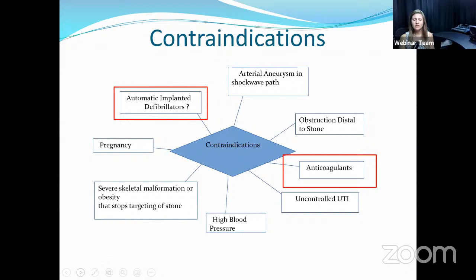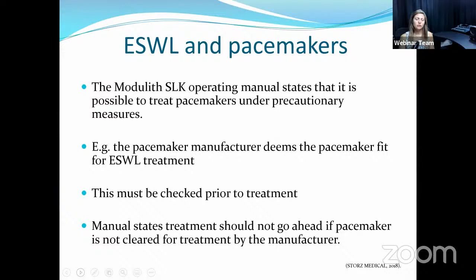contraindications during our progression of treatment, mainly pacemakers. So our lithotripsy machine is called Modulith SLK from Storz, and our manual just says that it's possible to treat a patient with a pacemaker under precautionary measures. For example, the manufacturer needs to deem that the pacemaker is fit for lithotripsy treatment, and this must be checked prior to the treatment. And our manual just states that the treatment should not go ahead if the pacemaker is not cleared for treatment by the manufacturer. So this unfortunately created a big gap in our knowledge, and we didn't know if we were able to treat the patient with lithotripsy or not.